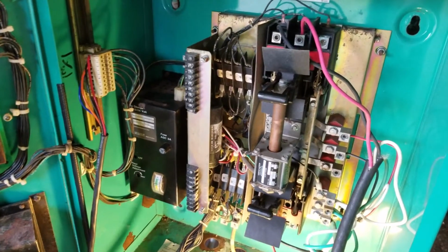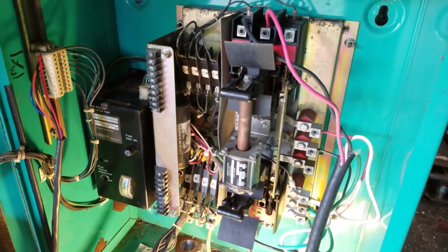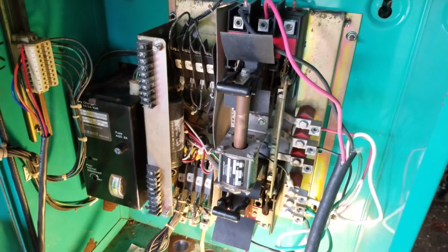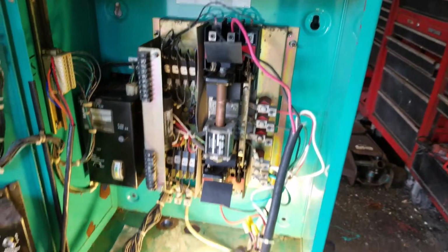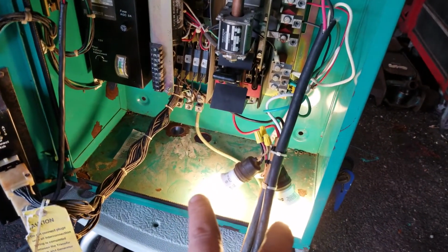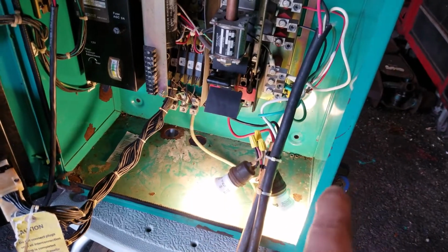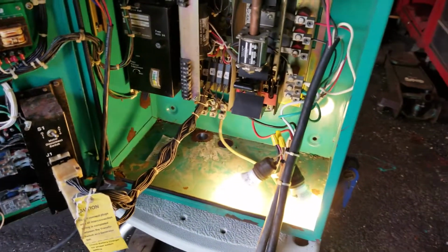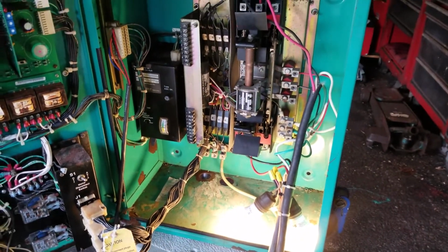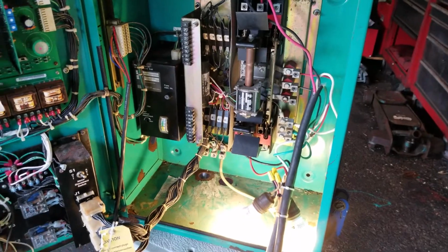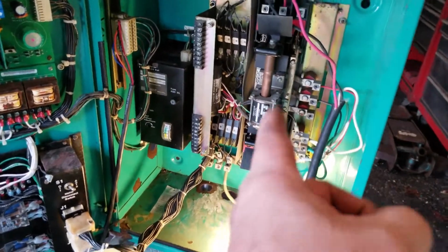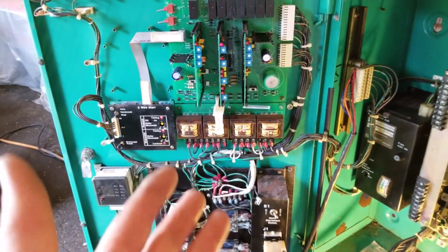Basically, to start off with, it's not sensing any of the voltages coming in, whether it's on the generator side or the line side. I hooked up two test lights, one for each leg. Right now it's hooked into my MIG welder outlet, which is 240 volts, so the transfer switch should be seeing 240 volts. The lights are lit and all that, however, the circuitry doesn't see it.